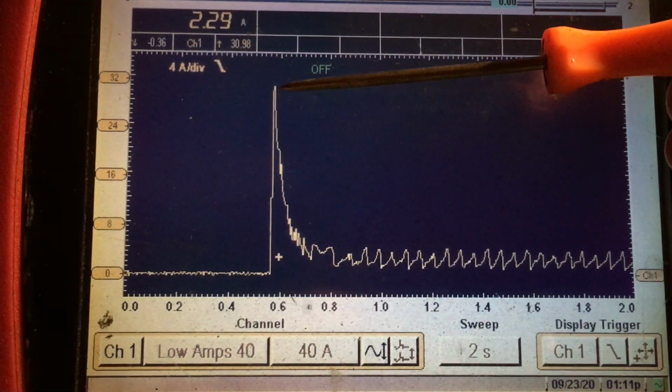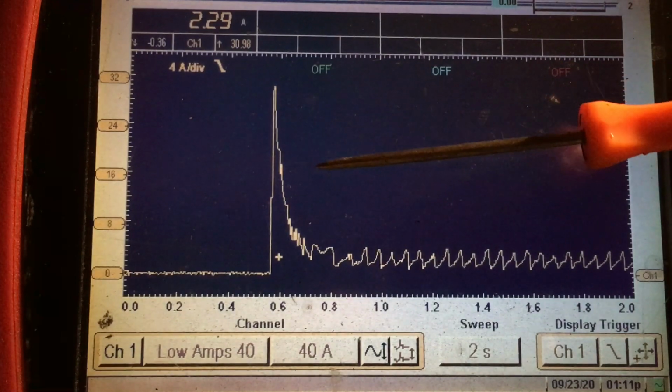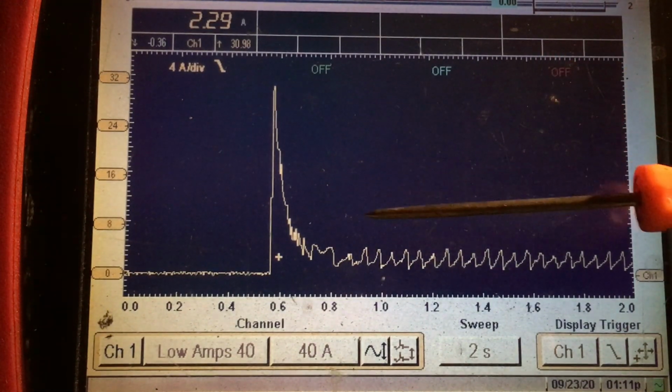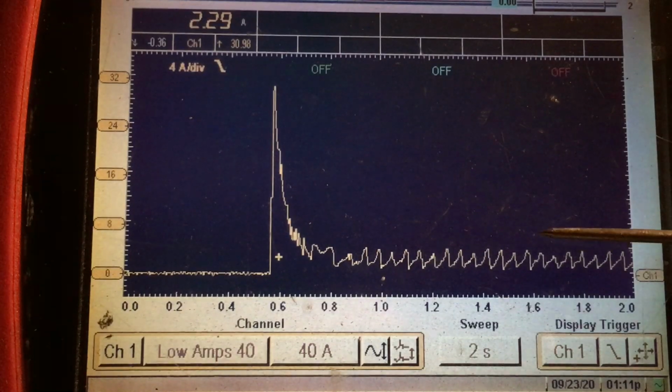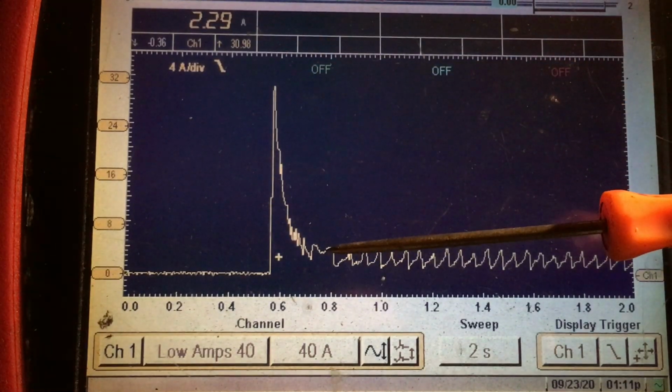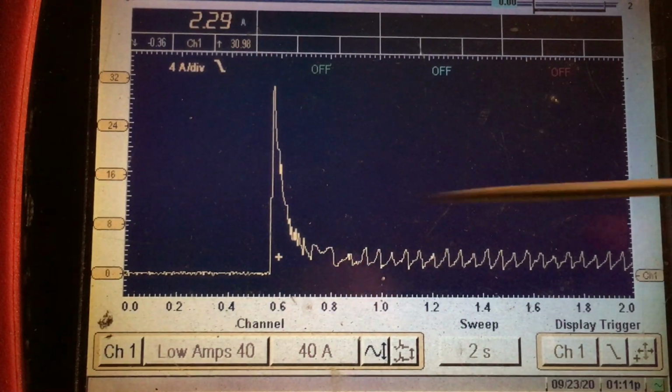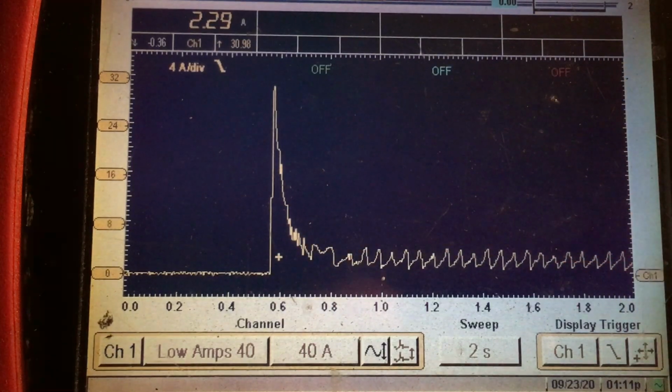But if we were driving something, and had to overcome the inertia of the system in order to get up to the nominal running speed, there would be a gentler ramp that would come down at a slower rate. This is dropping like a stone because it's reached its free running speed in no time at all, and it looks like a straight up and nearly straight down, as you can see.